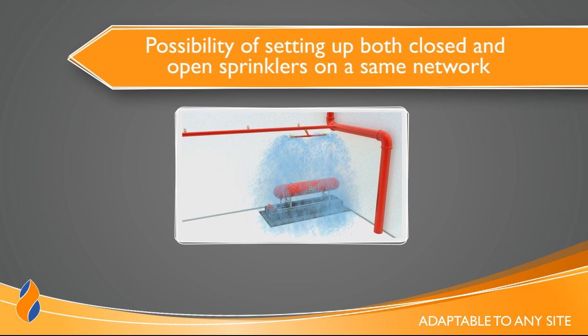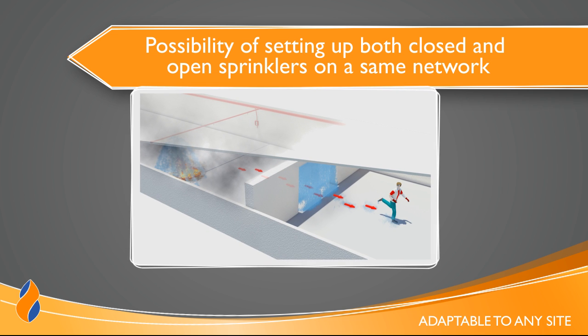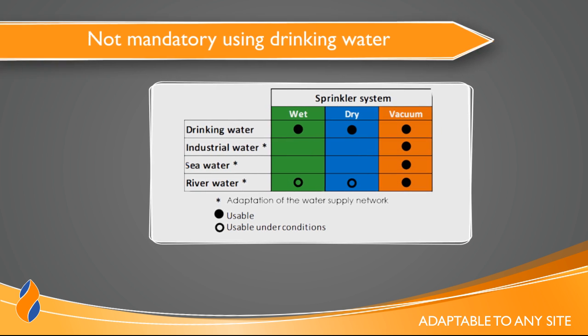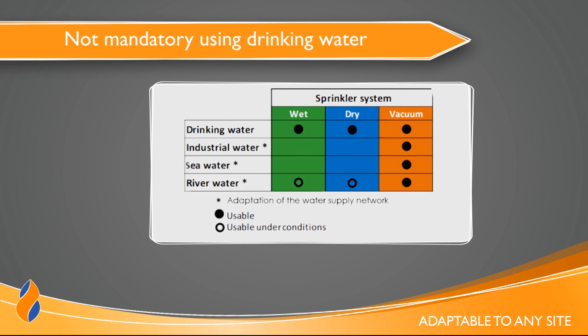The possibility to set up both closed and open sprinklers on the same network allows you creating a fire-stop water screen. This principle protects sensitive zones with high risks and has the advantage of isolating a fire while facilitating people evacuation. With the VACTEC vacuum system, you can use any water available on your sites to be protected. You no longer have to use drinking water. This also represents significant savings.